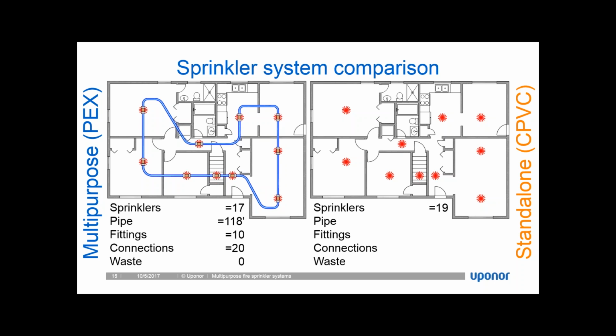The fittings, I have 10 sprinklers and I have 10 fittings. That means that I'm going to be able to take those sprinklers and bring them down to the ceiling level and use the flexibility of the tubing. I'm going to get to that on the next slide. I only have 20 connections. That's 1 connection on each side of those fittings, and I'm not including the threaded connections for the sprinklers on this comparison either.